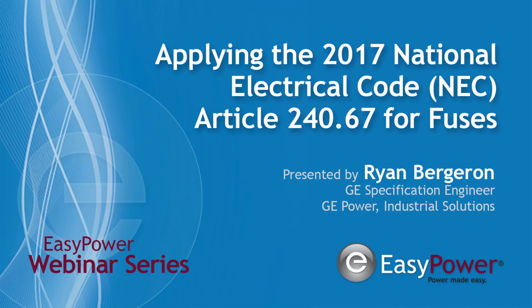I am honored to have this opportunity of helping you apply the new 2017 NEC, National Electrical Code, Article 240.67, Arc Energy Reduction Paragraph for fuses 1200 amps or higher. This will be applicable for the new electrical safety requirements for any facility adopting the 2017 NEC, such as commercial, industrial, data centers, or healthcare type facilities.